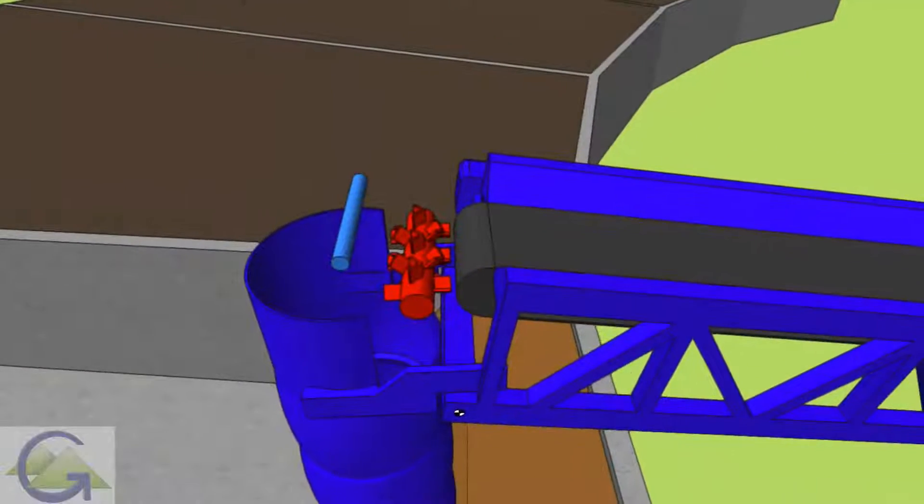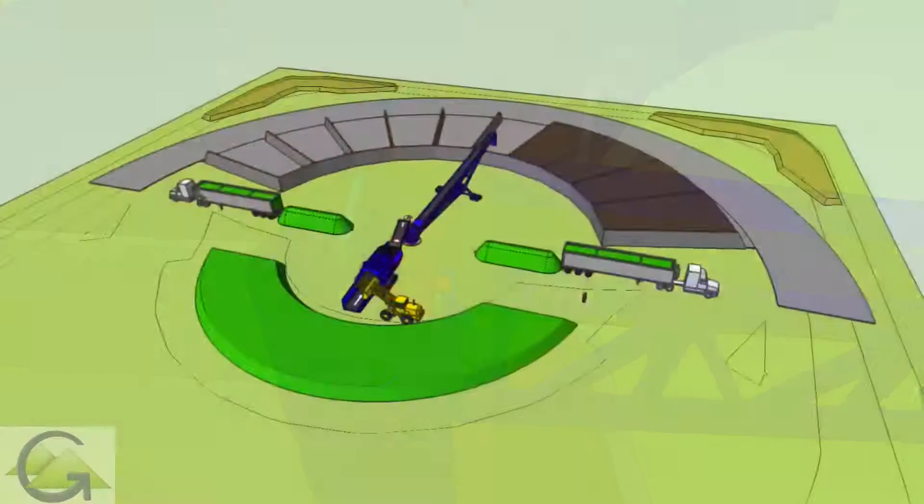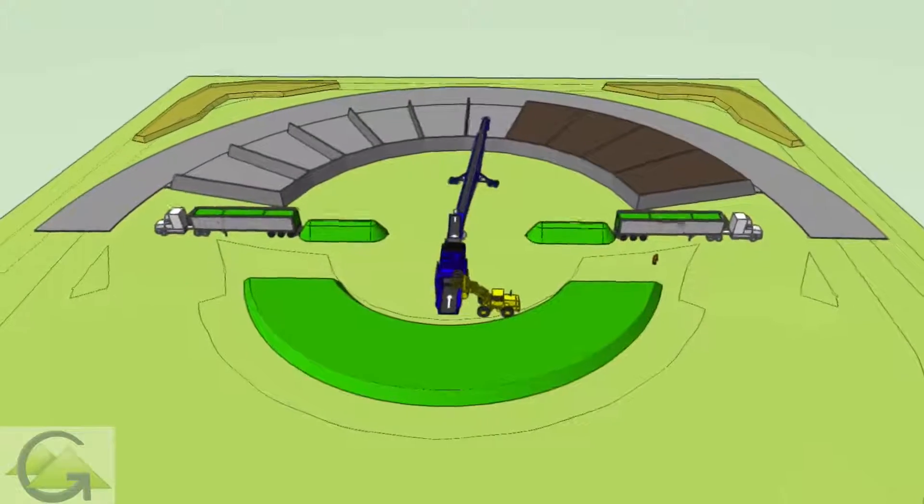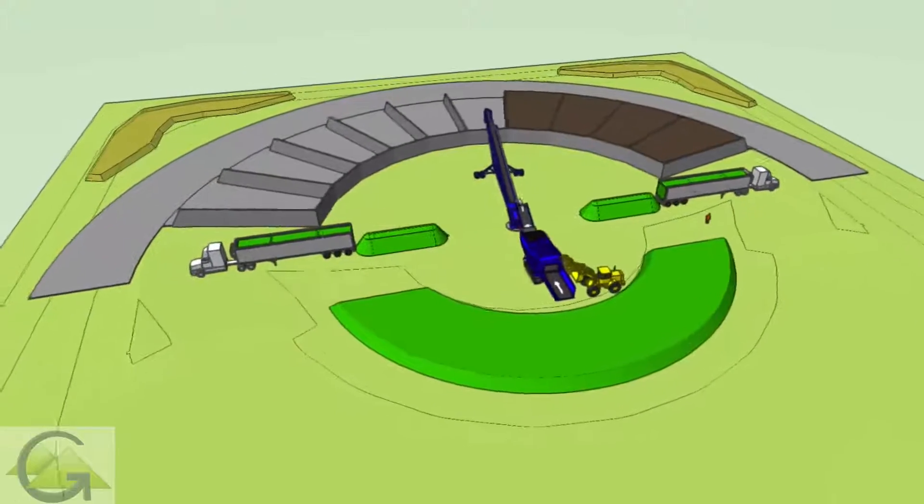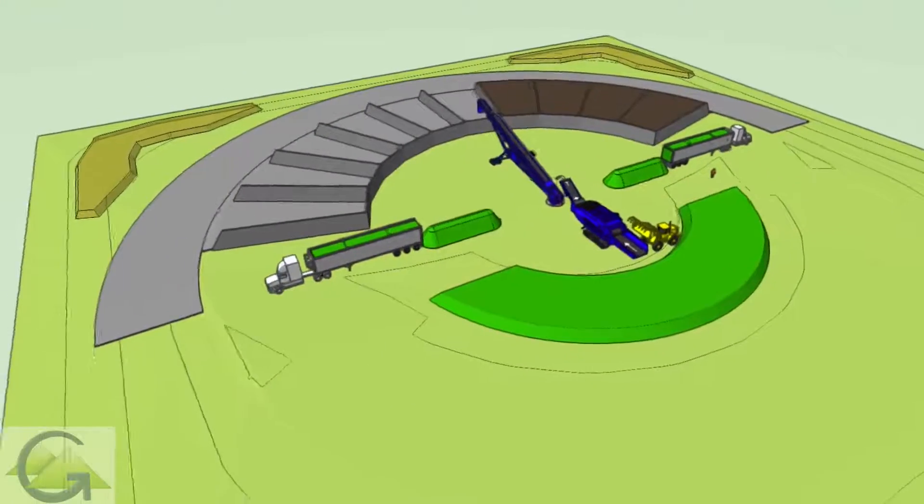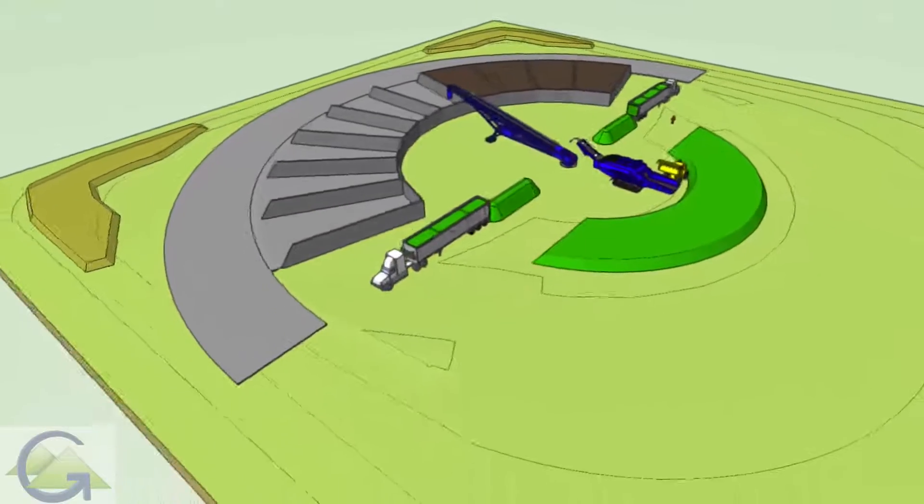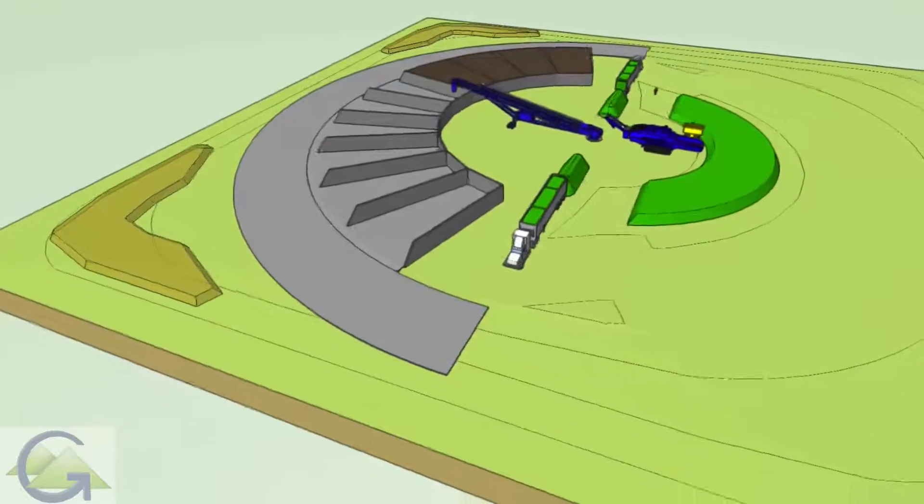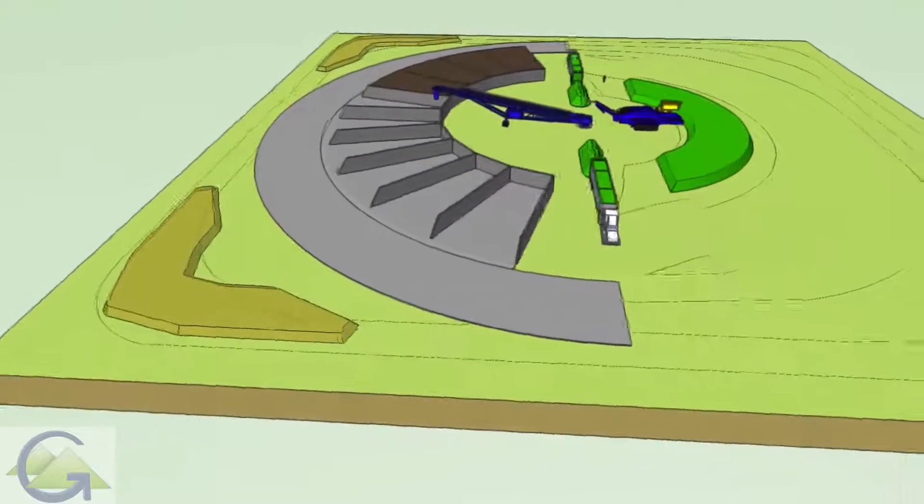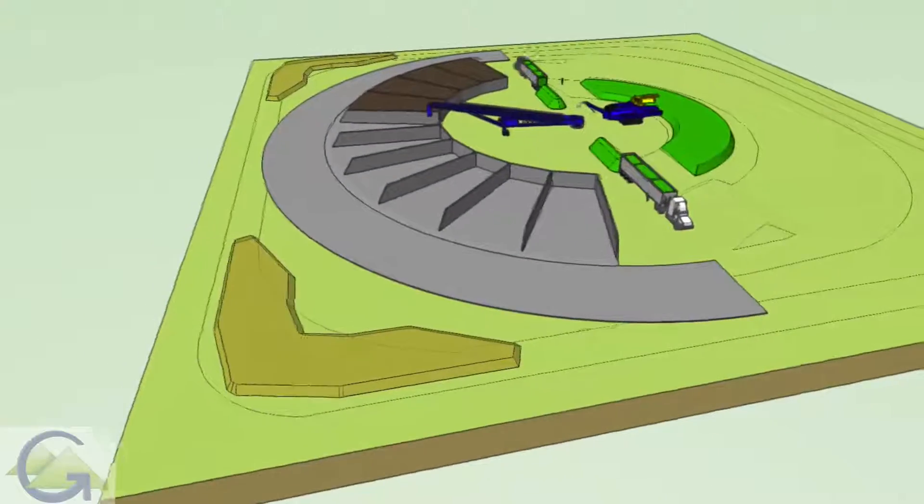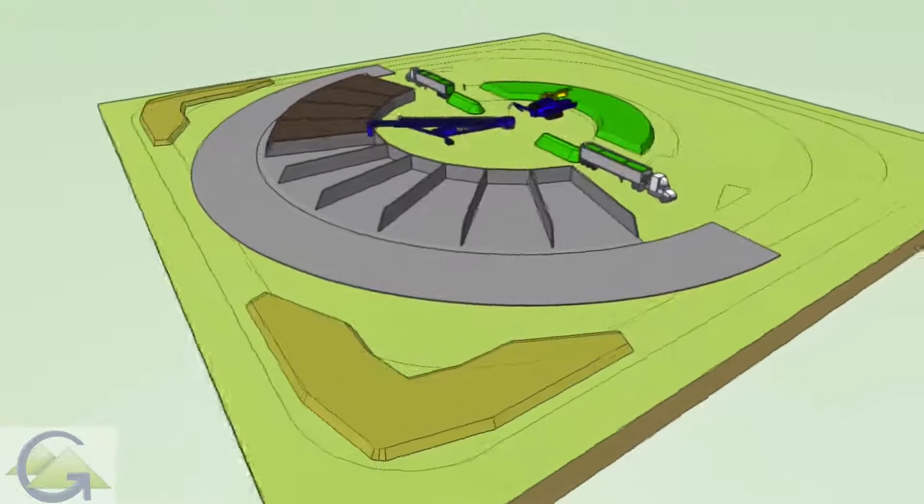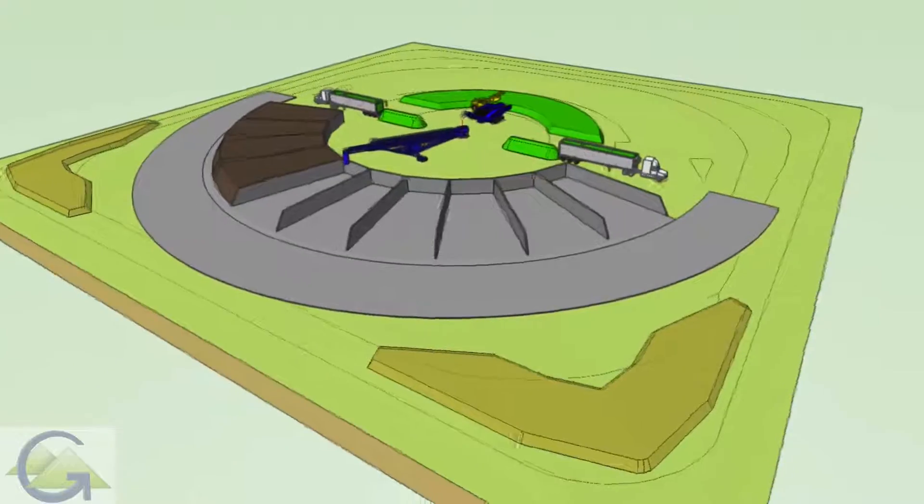Water can be added at the flail, thus eliminating sticky conveyor belts. Stormwater and leachate management is a critical aspect for composting facilities. Moisture from the piles, or condensate from the aeration pipes, is collected in manholes that drain by gravity to a chopper pump station. The pump is used to fill the stormwater storage tanks for treatment and reuse as needed.